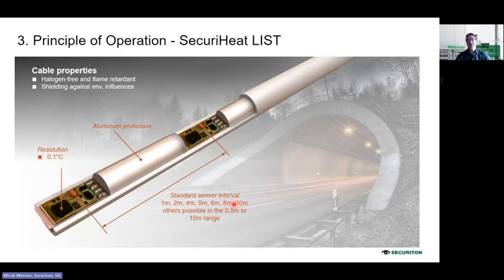Usually when we use the cable for rail and road tunnels protection, 8 or 10 meters is enough. Usually 10 meters is the most standard distance we use. If we have an industrial application where you have sections where you have to use another spacement, you can use 1 or 2 meters. But also we can manufacture the cable customized in a distance you also need. Then we have the resolution, which is quite impressive. It's 0.1 degrees, so it's a really exact measurement of temperature.